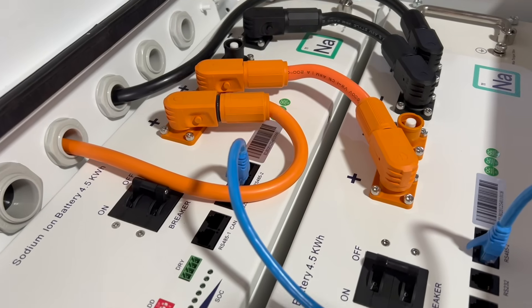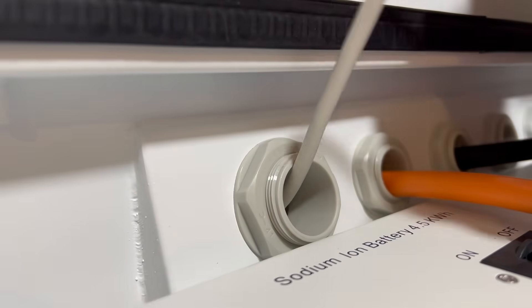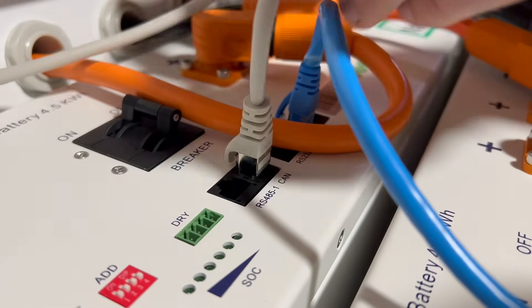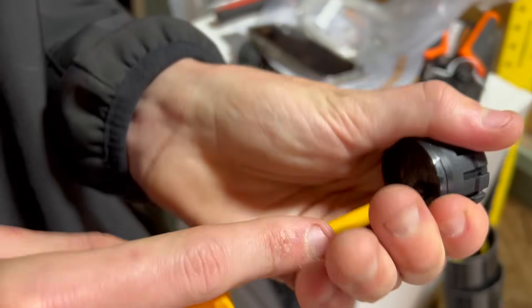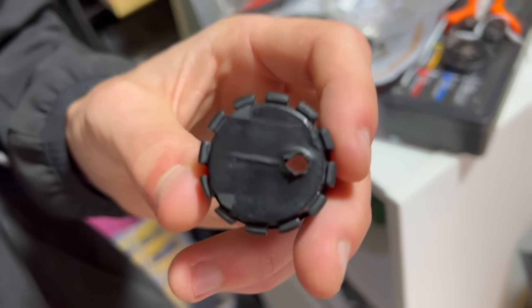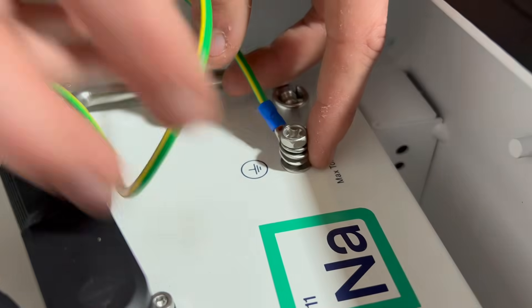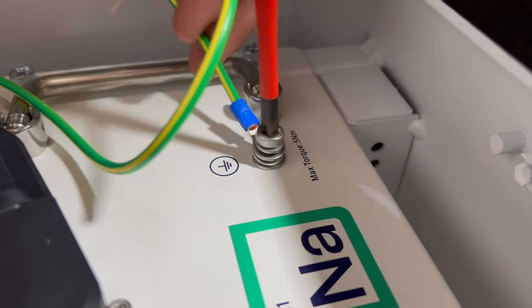Because we've got two batteries for this installation to give us about nine kilowatt hours of storage, we need to connect them together, and exactly for that purpose we've got these two linking cables that connect the batteries together and allow for the larger capacity to be filled. Now it's time to make sure the batteries can communicate with the inverter. We do this by means of a pre-terminated data cable that just plugs into the relevant socket on the first battery. There's so much thought going into the design of this system that there's even a specialised gland on the back with multiple smaller holes that you can pop out to accommodate the thinner cables.